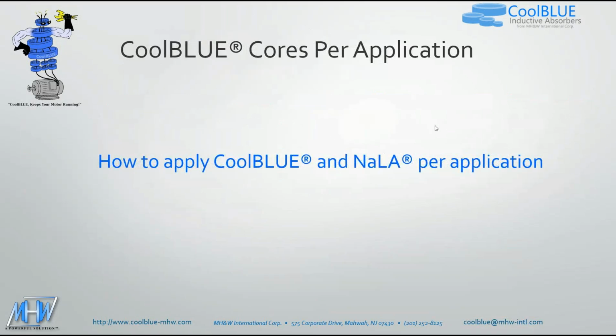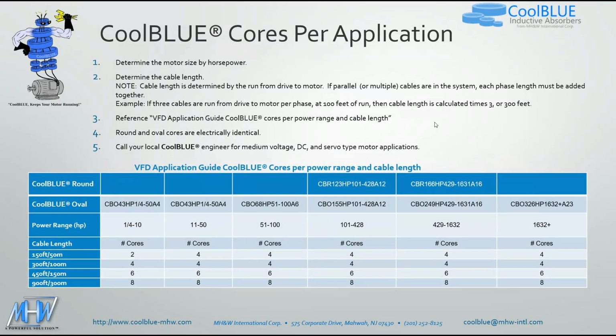Okay, go ahead. Yep. So we'll talk real quickly about basically how to apply CoolBLUE and NALAs per your application. First, you determine the motor size by horsepower. Then you have to determine your cable length from the VFD to the motor. And note that if you have parallel cables in the system, then each phase has to be taken into the calculation. For example, if the cables are run from a drive to a motor per phase at 100 feet of run, then the cable length would be calculated as 3 times, or 300 feet.